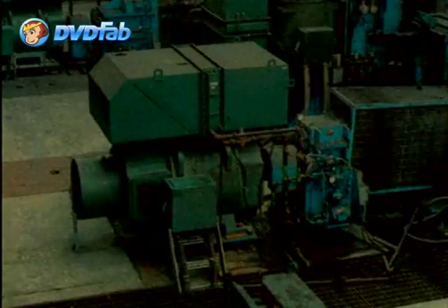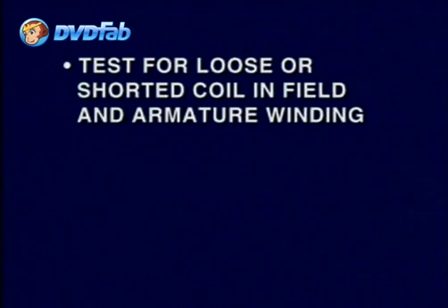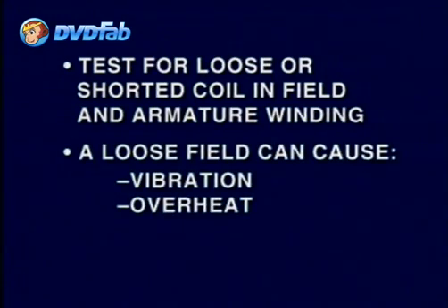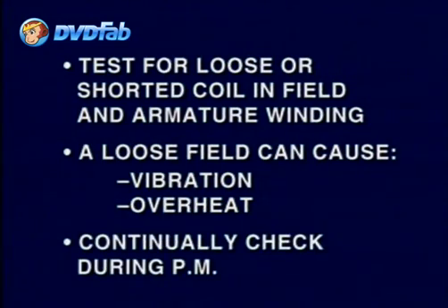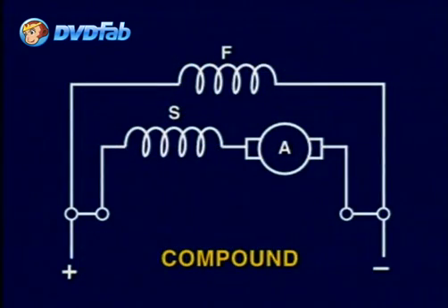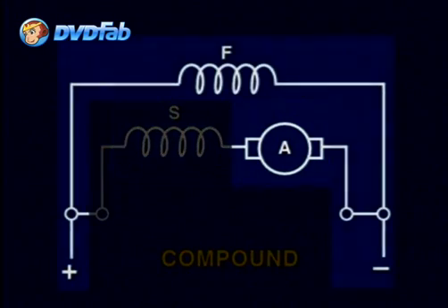If the shunt motor does run but heats up or starts to draw too much current, it should be tested for a loose coil or a shorted coil in the field and armature winding. A loose field can cause the motor to vibrate and overheat and should be checked during preventive maintenance to ensure that they do not come loose. The same applies to the armature. The compound DC motor, as we know, is a combination of the series and shunt motors, and its troubleshooting should be done using the same methods as the ones used in the series and shunt.